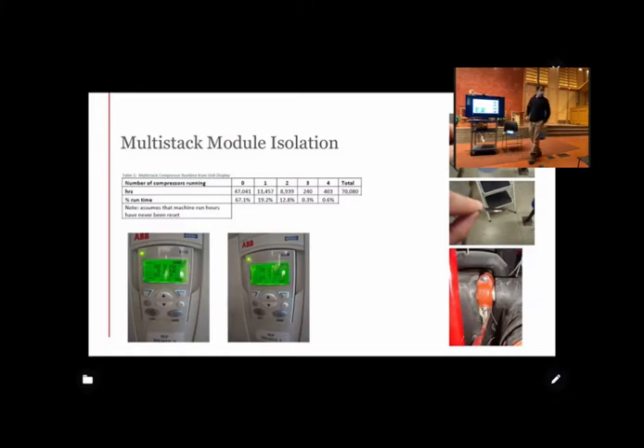Mike, you might want to mention, we instrumented the current going into each of those units. So we created charts showing that many times we'd see short cycling, like 5 minutes on and then right off, with a lot of those units, and that on its own was very interesting.